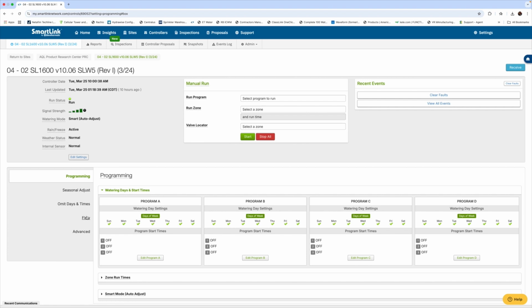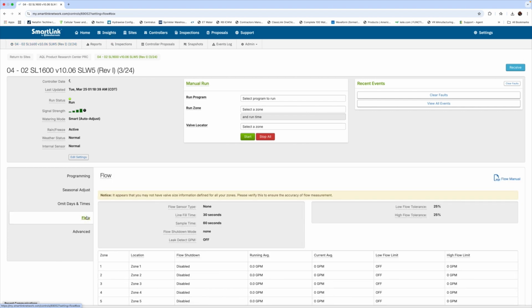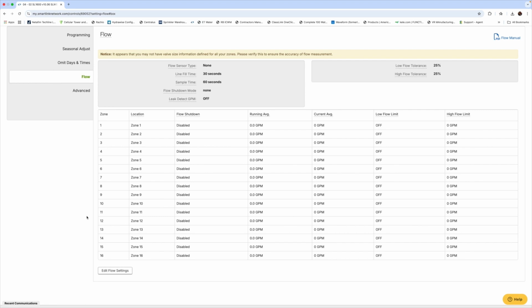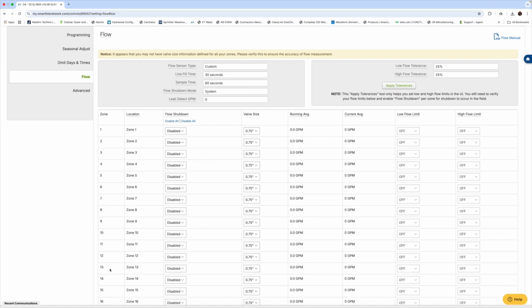Now, note, you've got to add flow to your subscription in order to access the flow menu. So if you haven't done that, please jump into your subscriptions portion of the controller you're working on and add the flow subscription to your controller so that you can get started. So this is what you're going to see when you open up the flow page if you haven't configured anything once you get that added to the network. And so we're going to click on Edit Flow Settings.